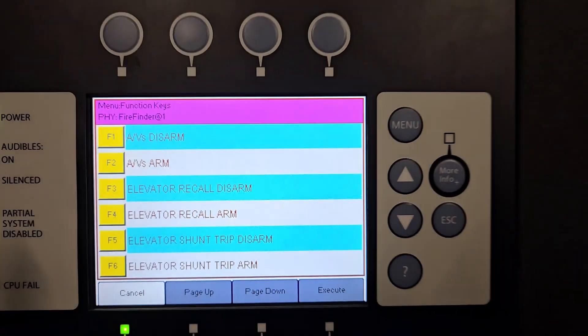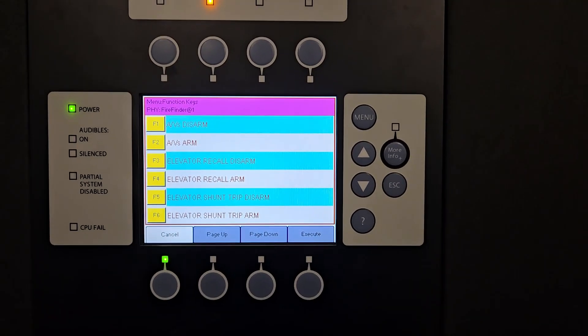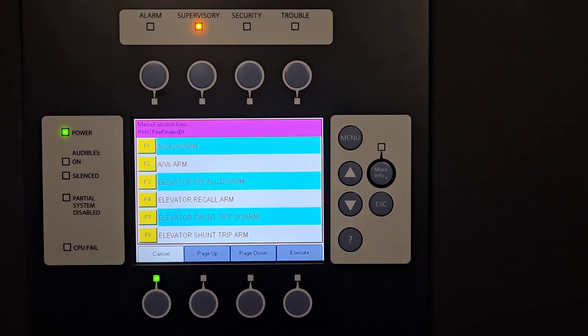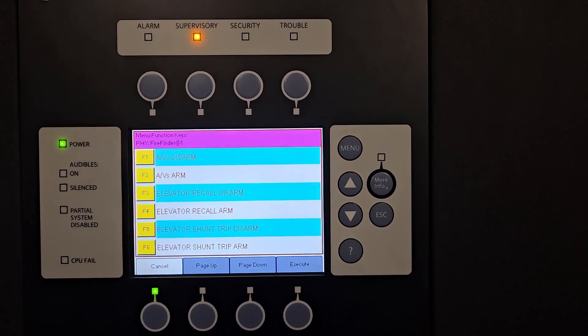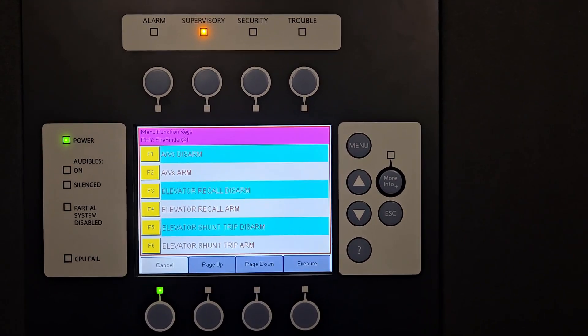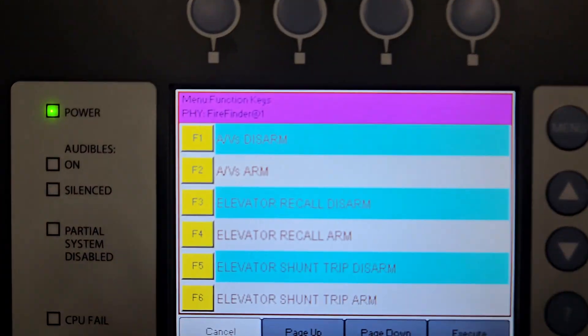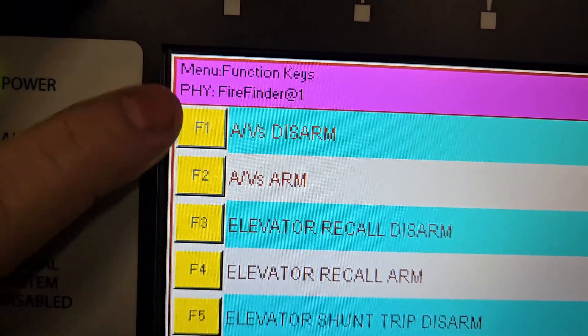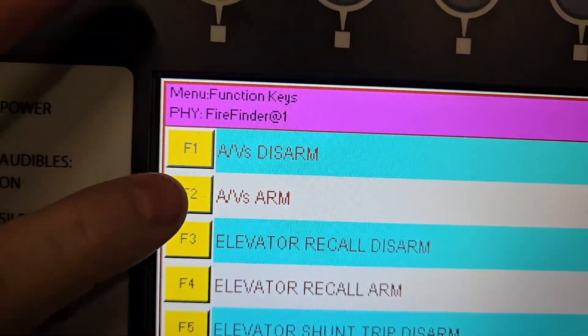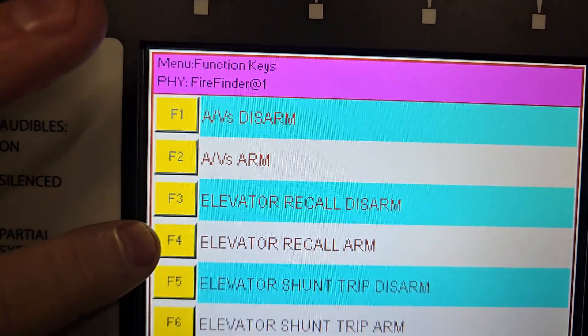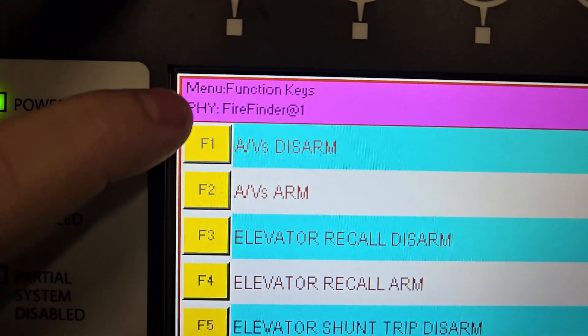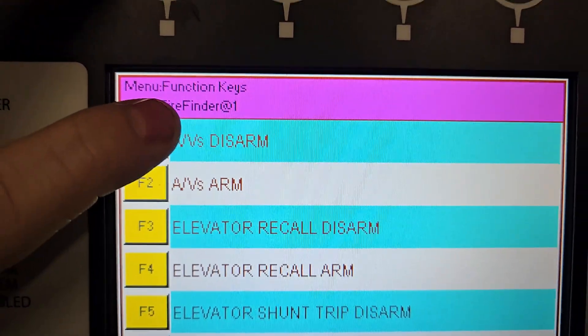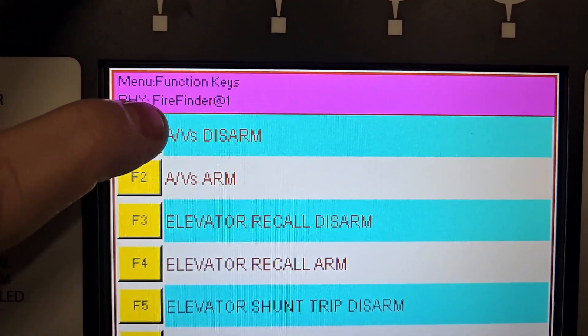What we want to do for the purposes of this video is disable our AV, or audible circuit, so that when we test the fire alarm system, no horns or strobes will activate. You have disarm and arm. Currently, because I have nothing disabled, everything is technically armed. So I want to disarm the audio-visual — this is a touch screen — so I'm going to hit F1.